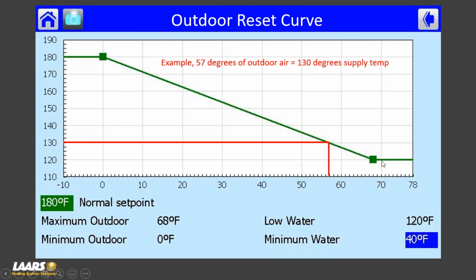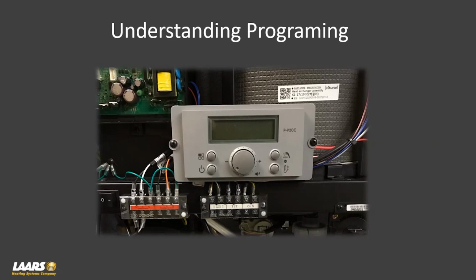And keep in mind elderly people. Some elderly people at 70 degrees feel chilly. They want to take that chill out of the air. You might want to choose 74 or 75. If somebody wants to be very aggressive, maybe at 68 or 65 degrees of outdoor air, they want to be in a warm weather shutdown. So you customize this to your system.